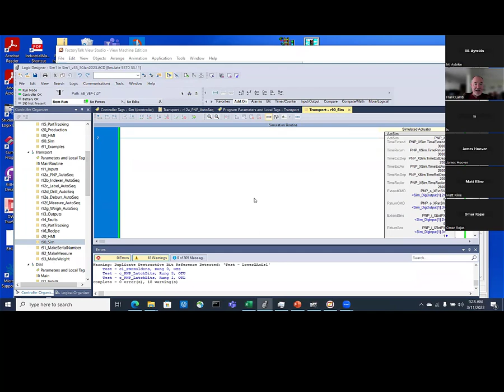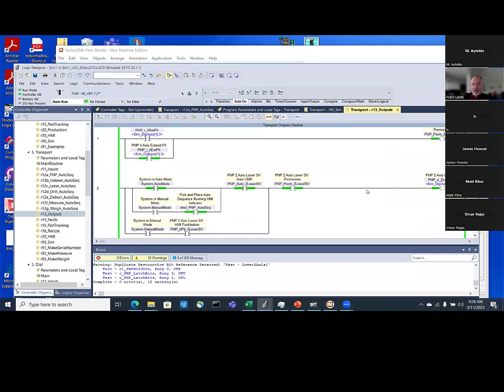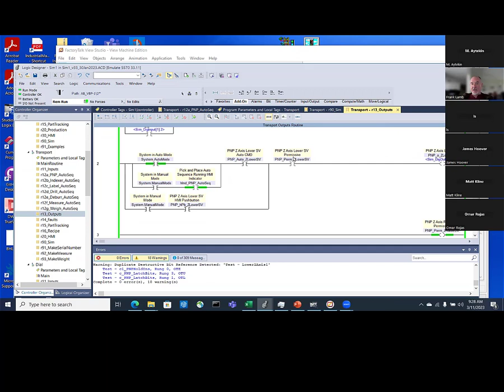Not this AOI, that's a whole different thing, but once you look at an output structure, you'll remember it pretty well forever, right? You have a coil with an output, you have some kind of a permissive saying this is allowed to do this. If the sensors aren't in the right condition, you don't want to break things. So if you're writing programs, one of the first things you do is make sure your permissives are correct so that things can't break other things. That's another proper use of simulation, because if you left out one of your permissives, you could actually run an actuator into another actuator. That would be bad. So that's one of the purposes of these simulations.